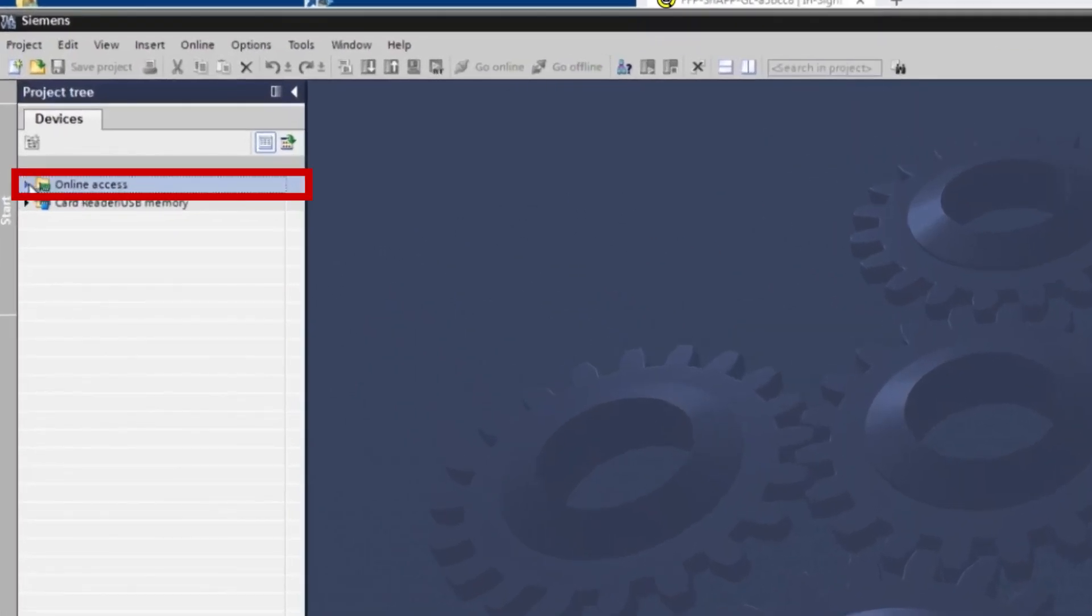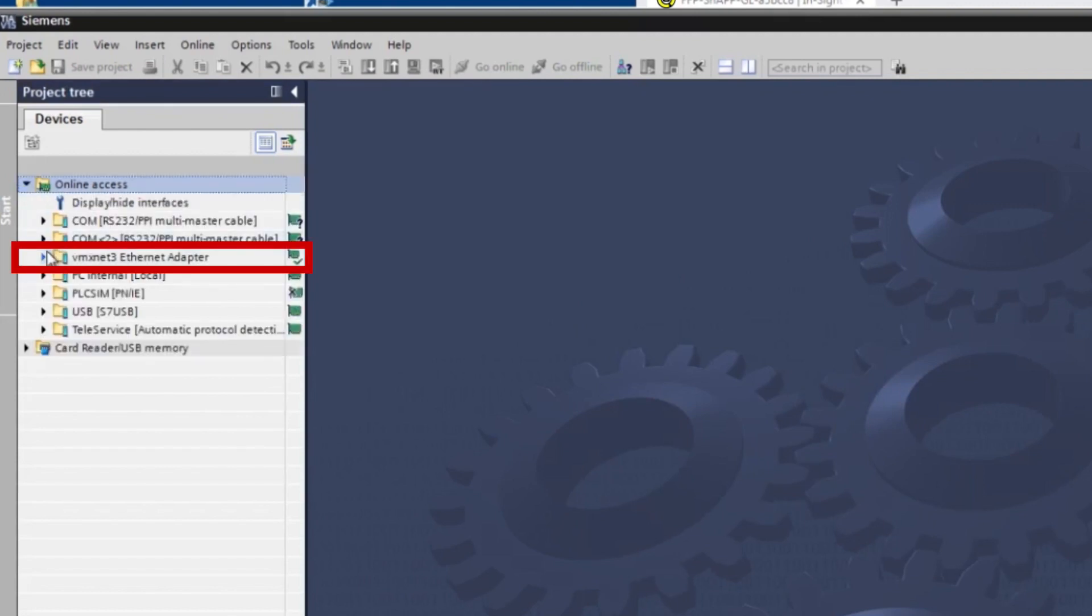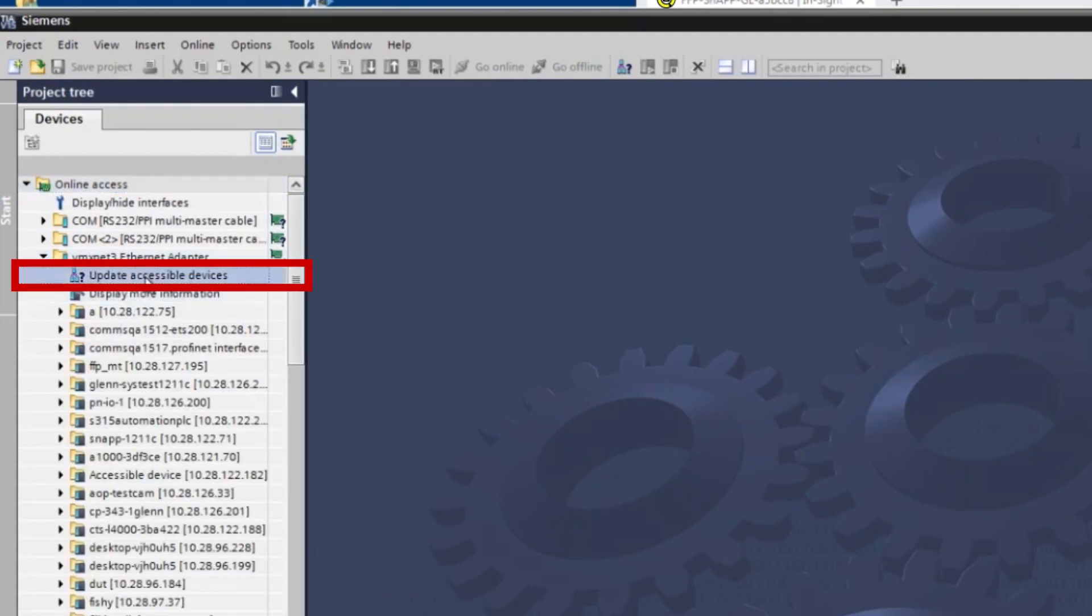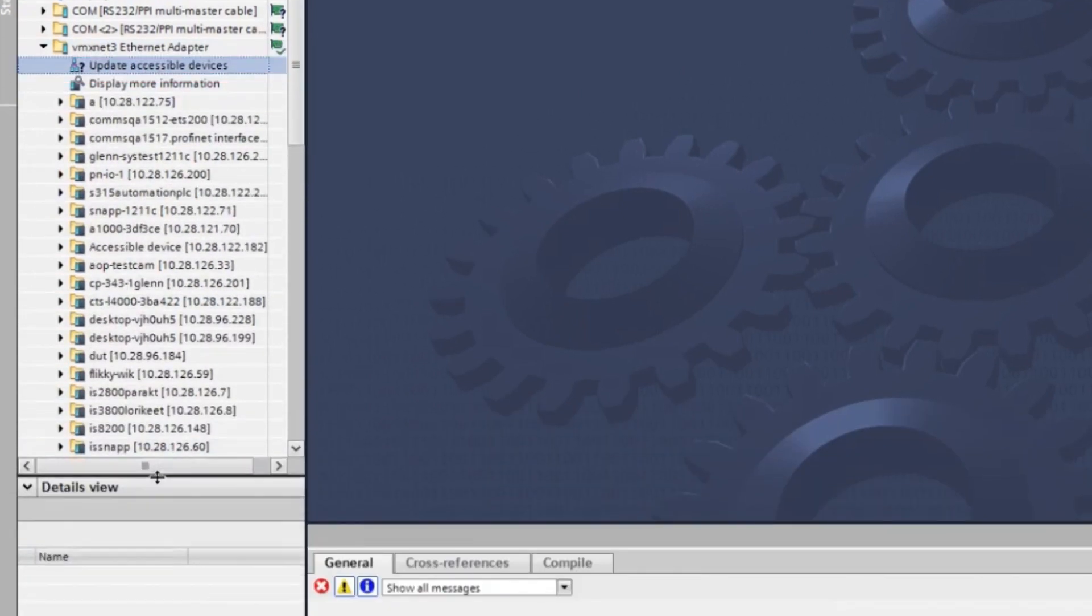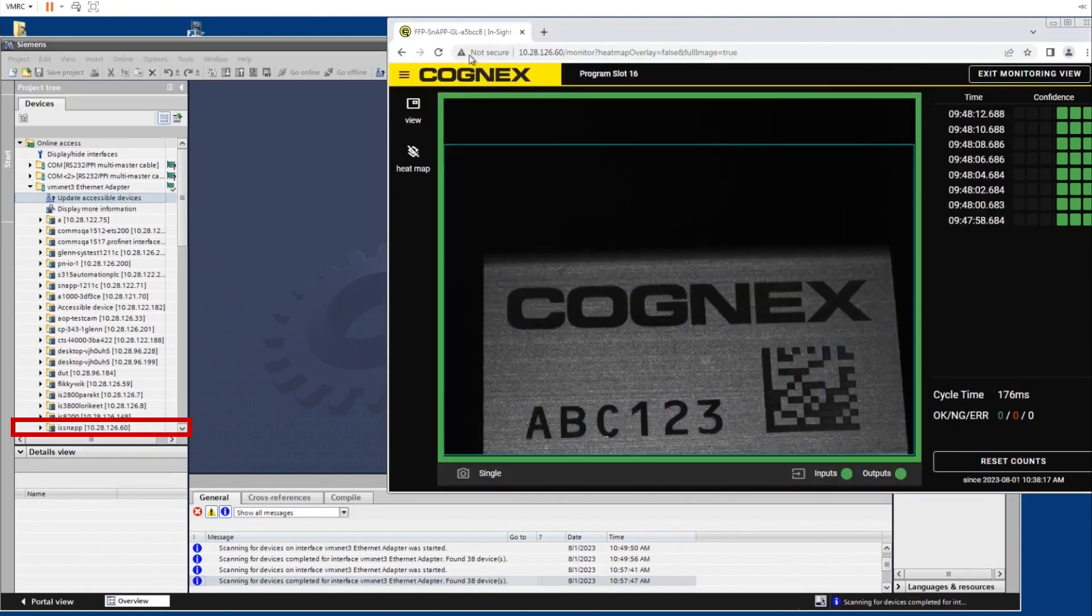To confirm PROFINET is running and the device can be seen on the network, locate and expand the online access tab. Find the Ethernet adapter tab and expand the drop down menu. The InSight snap sensor is found on the same IP address that was being used previously. Expand the snap folder and click the online and diagnostics button to open. This allows us to see that the InSight snap has connected successfully.